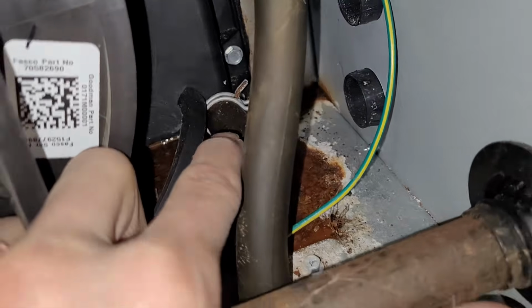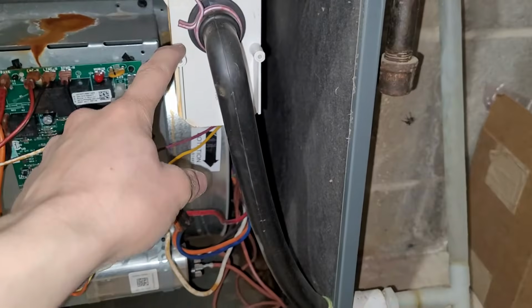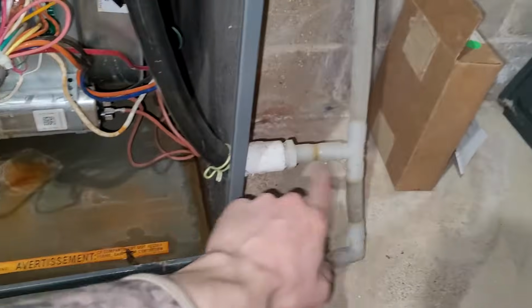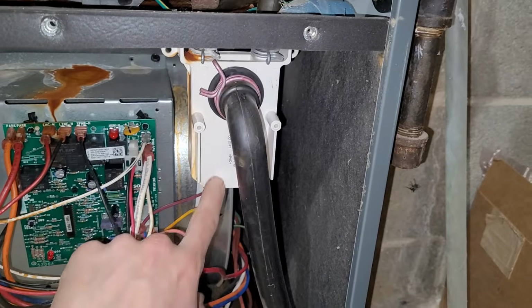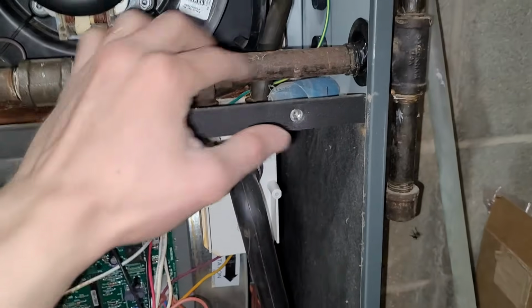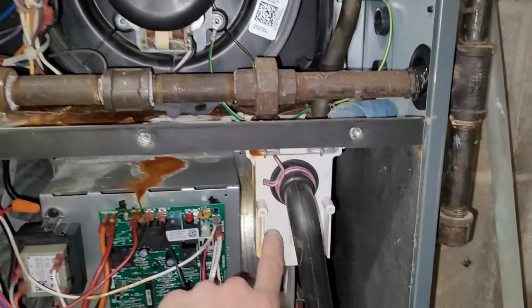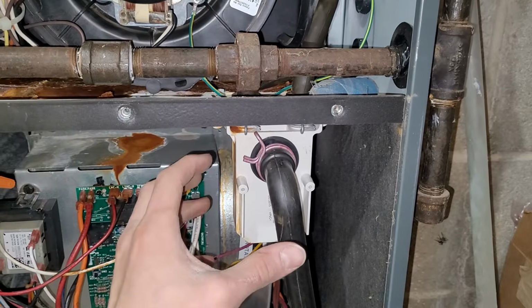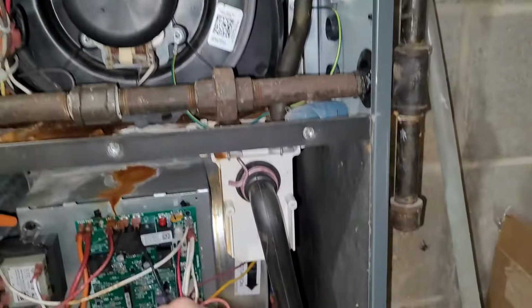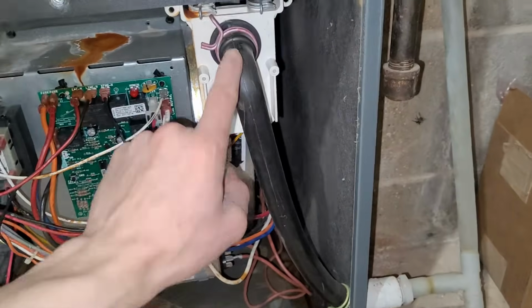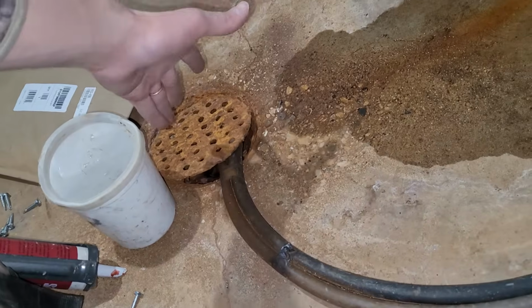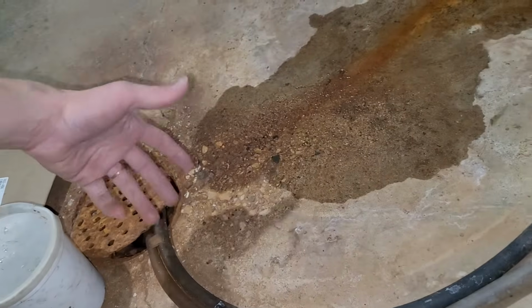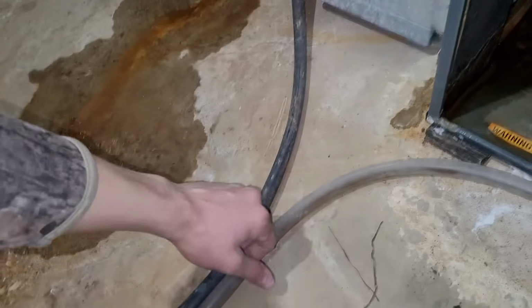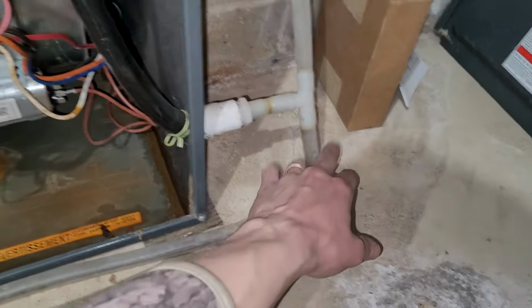So that port right there drains here into this trap, and then it drains out of the trap and into here. If your trap gets plugged up with debris, it can back up and end up leaking out on the furnace. So you need to pull your trap and clean that out if that's plugged, causing it to leak somewhere up here. Otherwise, just like a loose connection somewhere. And then it can also be plugged somewhere in this condensate line, wherever that ends up going. Usually it goes to a floor drain close to the furnace. Yours could go to any number of places though. So that's what you'll kind of want to check first. Best case scenario, you just have like a plugged tube or something like that.